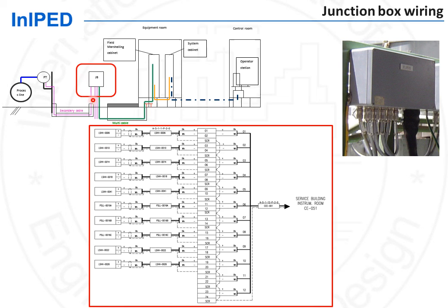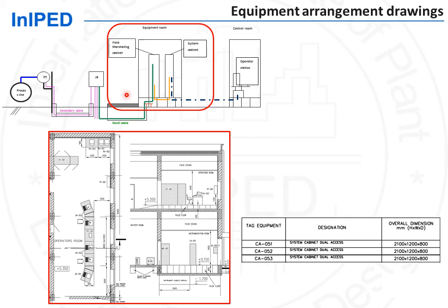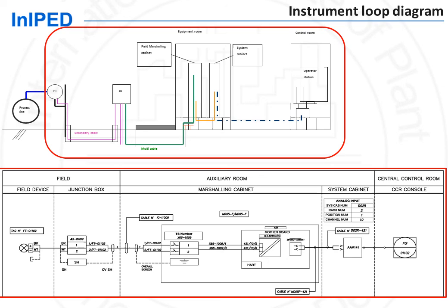The junction box wiring diagram shows the connections between secondary and multi cables. The equipment arrangement drawing shows the layout of the instrumentation equipment room and the position of the various cabinets. Finally, the instrument loop diagram shows the complete connections for one particular instrument, including numbering of terminals, cables, I/O cards, and so on. This drawing is used for pre-commissioning to test the functionality of the instrument and during troubleshooting.